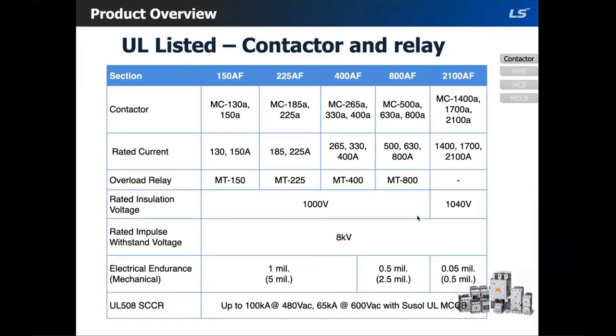There are 10 different frame sizes. Here you can see the last 5. Each frame size has a group of contactors within them. So for example, if you see 225 amp frame size, there is MC 185 amps and 225 amps within this frame size. All 480 volt contactors have a short circuit rating of 100 kA, and all 600 volt contactors have a short circuit rating of 65 kA.